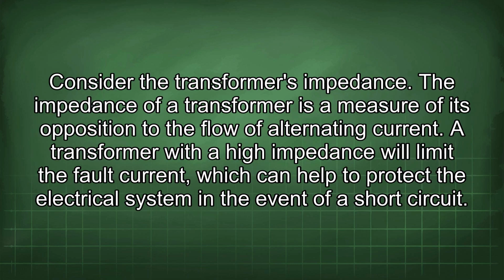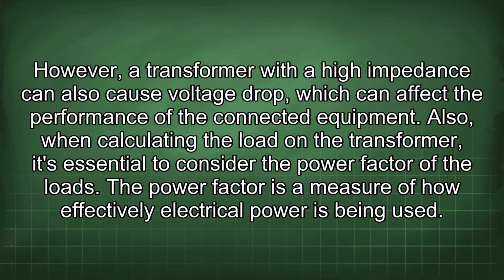Consider the transformer's impedance. The impedance of a transformer is a measure of its opposition to the flow of alternating current. A transformer with a high impedance will limit the fault current, which can help to protect the electrical system in the event of a short circuit. However, a transformer with a high impedance can also cause voltage drop, which can affect the performance of the connected equipment. Also, when calculating the load on the transformer, it's essential to consider the power factor of the loads.